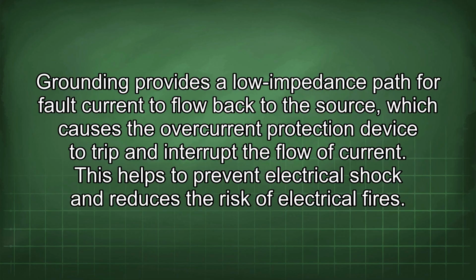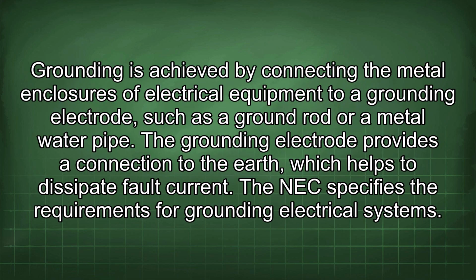Grounding provides a low impedance path for fault current to flow back to the source, which causes the overcurrent protection device to trip and interrupt the flow of current. This helps to prevent electrical shock and reduces the risk of electrical fires. Grounding is achieved by connecting the metal enclosures of electrical equipment to a grounding electrode, such as a ground rod or a metal water pipe. The grounding electrode provides a connection to the earth, which helps to dissipate fault current.